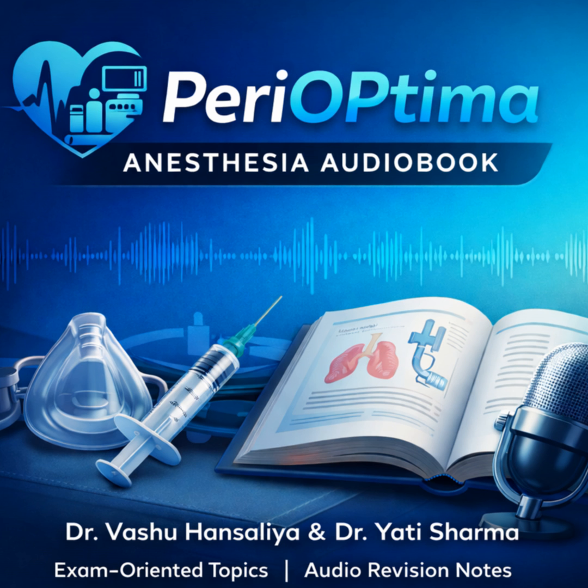Exactly. But if I select effect site targeting, the pump knows about the lag. It's smarter. It will purposely overshoot the plasma concentration, maybe driving it up to 8 or 10 micrograms per ml for a very short time, to create a huge gradient that pushes the drug into the brain much faster. Then it will pause the infusion to let the plasma drop back down as the brain catches up. So effect site targeting means a faster induction, but you might risk a bigger drop in blood pressure because of that initial plasma spike. Precisely.